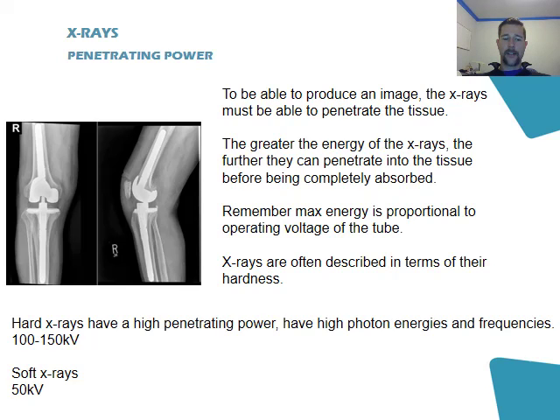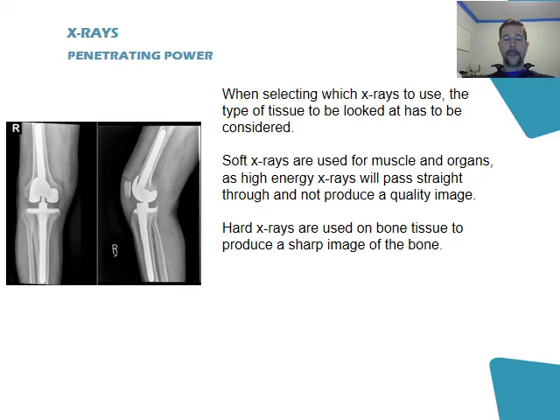Soft x-rays are in the order of 50 kilovolts. When we talk about kilovolts, that's the operating voltage of the tube — the potential energy across the tube. We usually select hard x-rays to penetrate bone, because bone is a very dense material, whereas we use soft x-rays to penetrate muscle to get a better image.